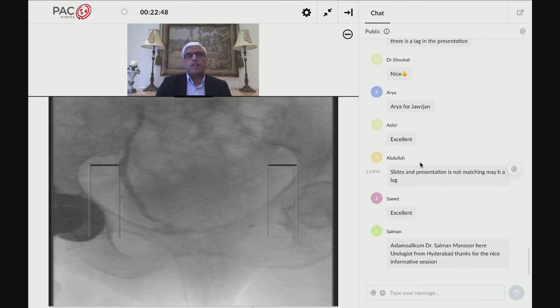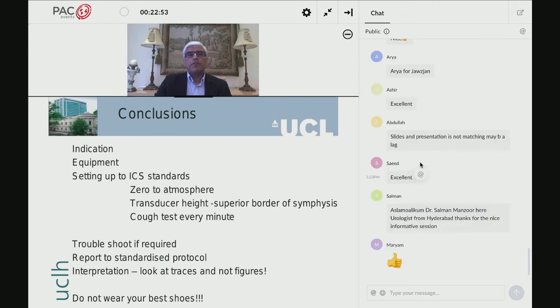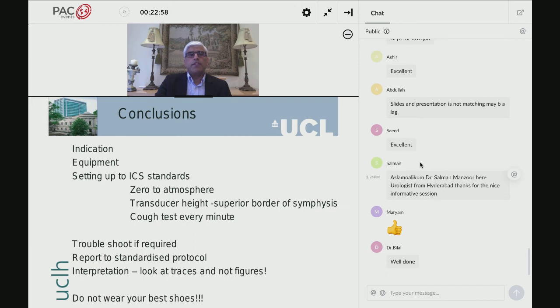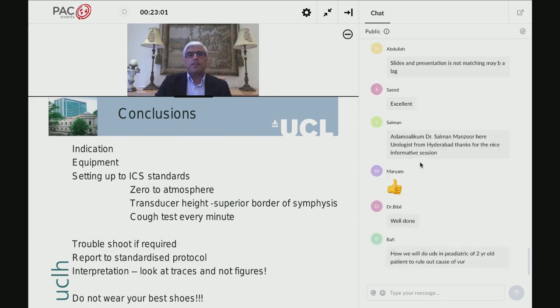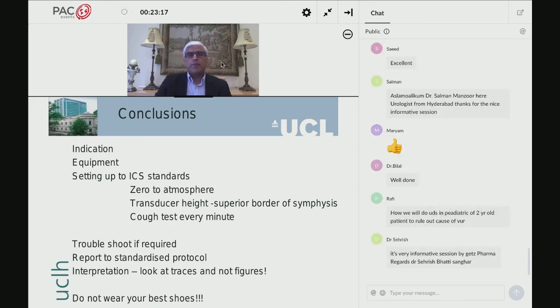But in conclusion, we need to know what is the right indication to do the urodynamics. We should not just have the right equipment, but we should be familiar with our equipment, and set it up to the ICS standards, i.e. zero to the atmosphere, make sure that the transducer height is at the superior border of the symphysis pubis, and do the cough tests every minute. Troubleshoot as required as we go along, and generally I say that it's a 2-person test so that help is available and we do not do a test which is invasive in a suboptimal fashion.